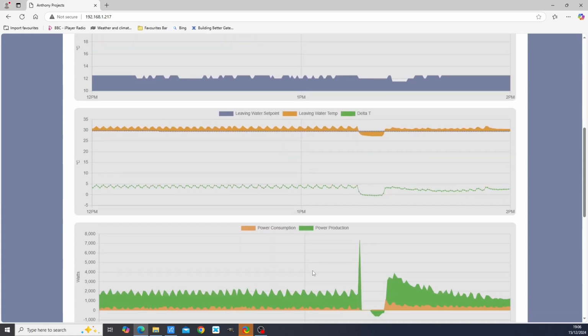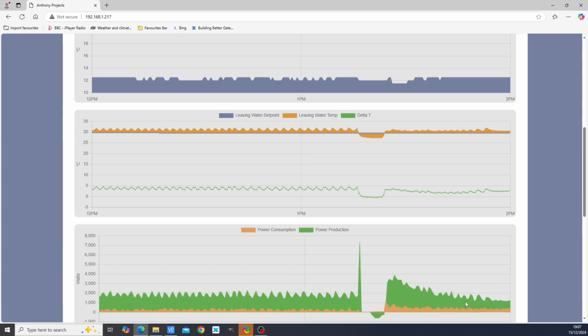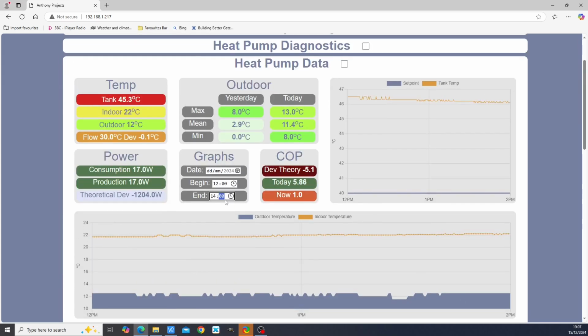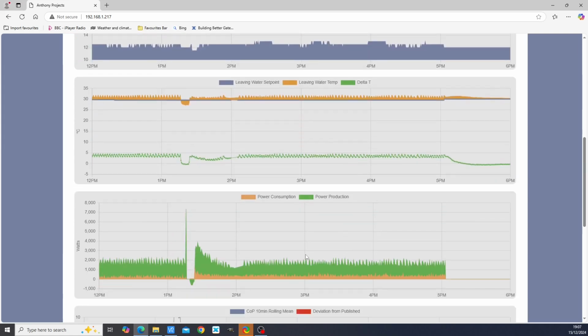I was really tempted to make a presentation at this stage and say that raising the leaving water temperature was the panacea in all of these instances, but actually it's not. What we're seeing is more of what we had on the 6th of November. We've got the compressor turning off and then turning on periodically. And that's the same behavior as before. And whereas here we've got the compressor running at a minimum continuously. And the output between the before and after case is exactly the same. So you go here, you can see the output here is exactly the same as the output here.